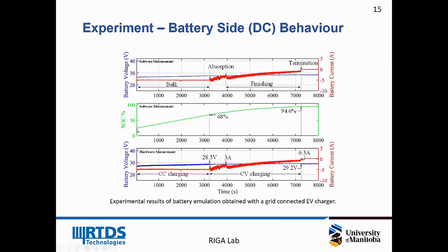In the very beginning, the SOC was around 25%, and there are two very well-known charging stages. The first one is constant current charging, and the second one is constant voltage charging. That is the built-in function inside the commercial EV charger. In the beginning, when the SOC is not high, the onboard charger provides constant current charging until it reaches around 68%. Now you can see that the voltage before that was increasing, until it reached this point, and then the voltage will stay constant, providing constant voltage charging, and the current is decreasing until it reaches 95%, and the EV charger will stop charging the battery.